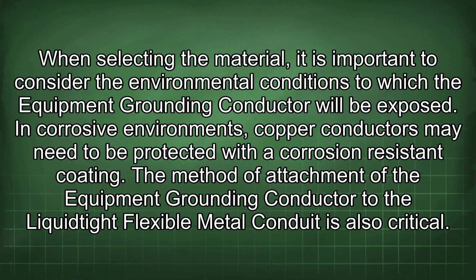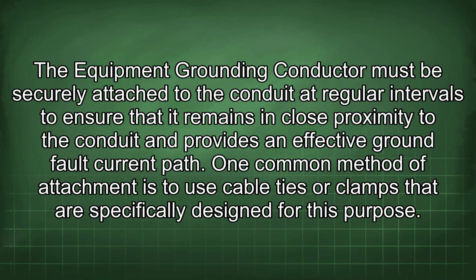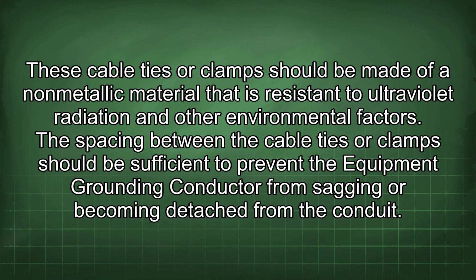The method of attachment of the equipment grounding conductor to the liquid-tight flexible metal conduit is also critical. The equipment grounding conductor must be securely attached to the conduit at regular intervals to ensure that it remains in close proximity to the conduit and provides an effective ground fault current path. One common method of attachment is to use cable ties or clamps that are specifically designed for this purpose. These cable ties or clamps should be made of a non-metallic material that is resistant to ultraviolet radiation and other environmental factors. The spacing between the cable ties or clamps should be sufficient to prevent the equipment grounding conductor from sagging or becoming detached from the conduit.